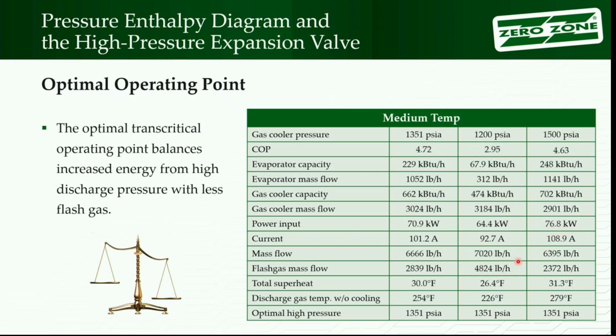Mass flow is kind of the same thing with, I'm trying to think which gas flow that is. Flash gas mass flow, again, this is where you see that huge number pick up, right? When I started dropping down on that line, I start moving to the right really quick, I get a lot of flash gas. So you have a lot of flash gas being generated with that. Superheat drops down a little bit. The reason superheat drops down is as you generate more of that flash gas, it's actually cold flash gas. It'll actually be a little bit wet, a little bit damp. So as I put more of that load into my system, that's going to make the overall suction colder.